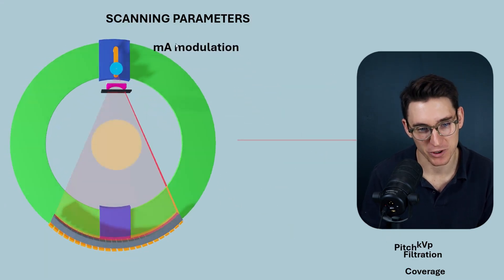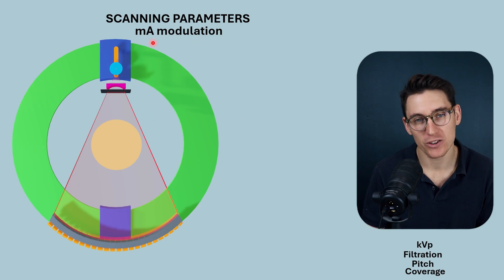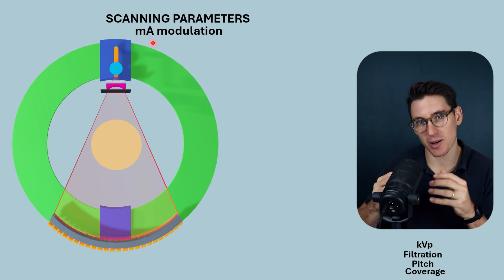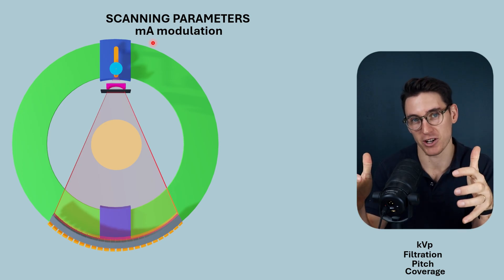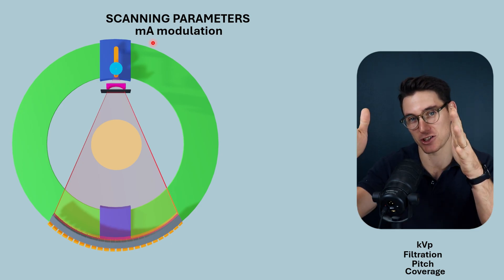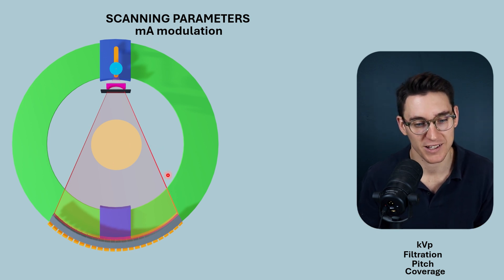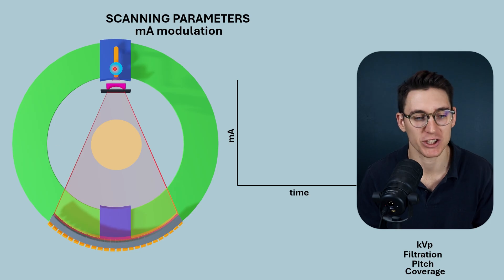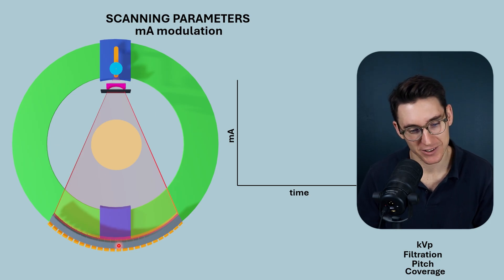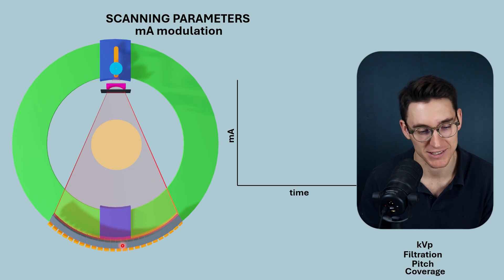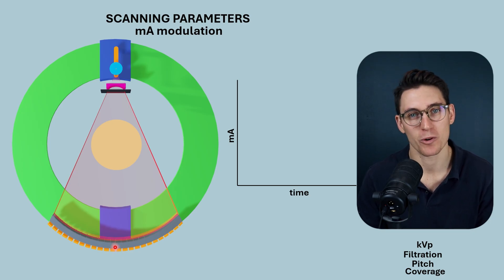The next factor is current modulation — milliampere modulation. If we modulate the current passing through the tungsten filament within the cathode, we change the number of electrons available at the surface of the filament through thermionic emission, and ultimately change the number of electrons accelerated towards the anode, which in turn determines the number of x-ray photons heading out towards the patient. If we plot a graph of current on the y-axis and time on the x-axis whilst the CT machine rotates around our patient, a sensor by the detectors could sense how many x-ray photons are being received.